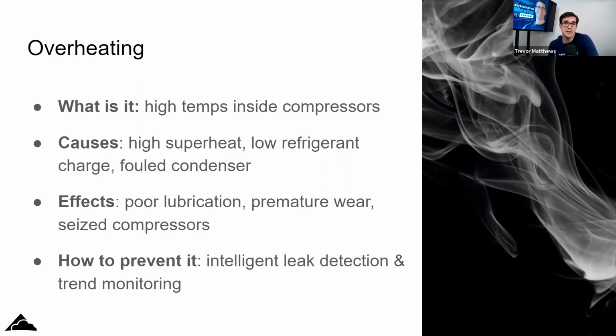Really what the technician needs to understand is that anytime the compressor is running outside its envelope, it's damaging the compressor. These manufacturers that are building these compressors, they're building them for 15 years. But I've seen them fail in 2 years, 3 years, 5 years. And what the compressor manufacturers have done, like Bitzer, Copeland, Danfoss, all of them, they're adding features for customers to buy to protect them a little bit more. DLTs, which is discharge line temperature protection. So if that temperature gets too high, it shuts down the compressor. Because when that oil starts to overheat, you have a world of problems.